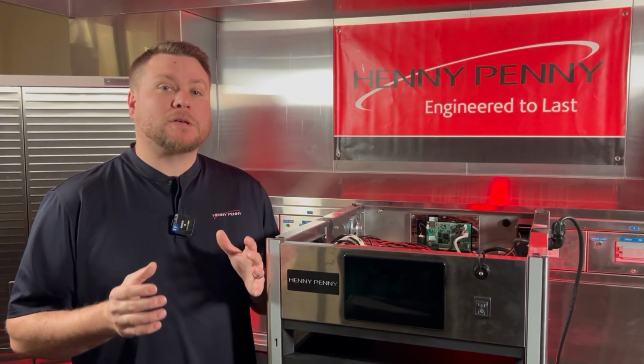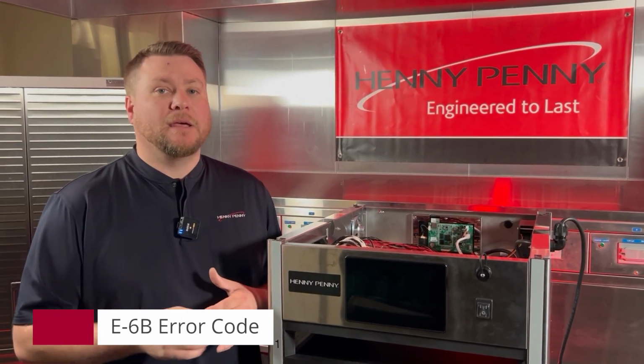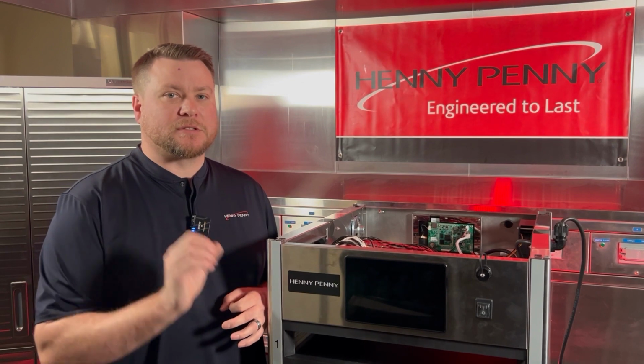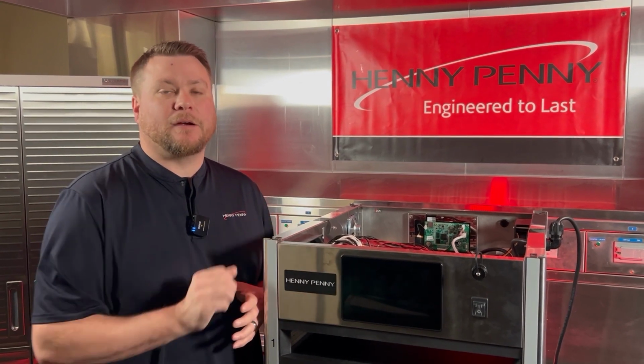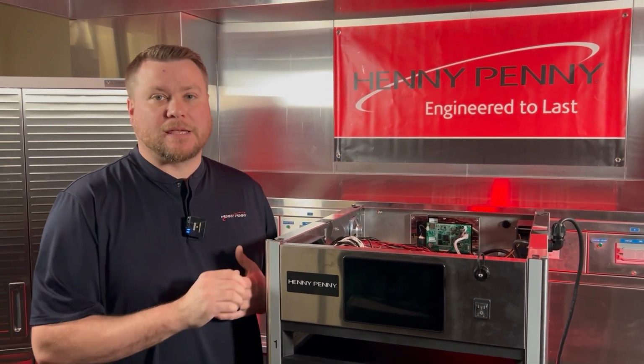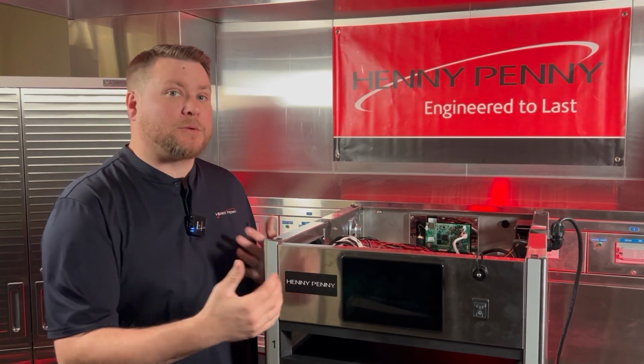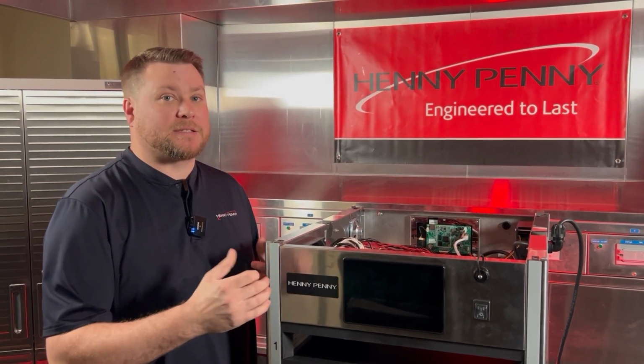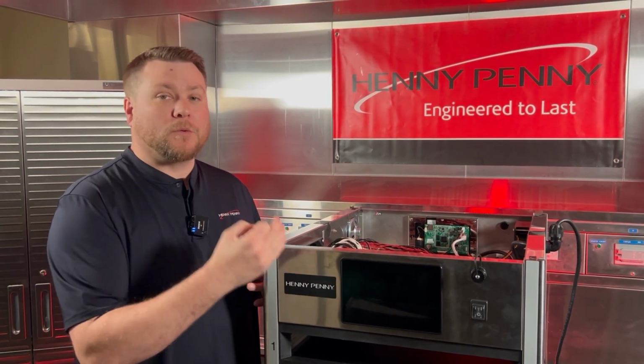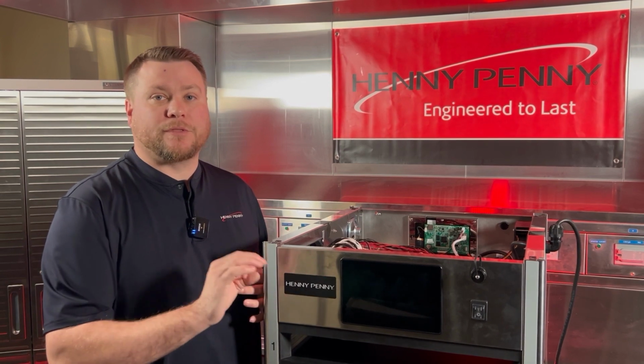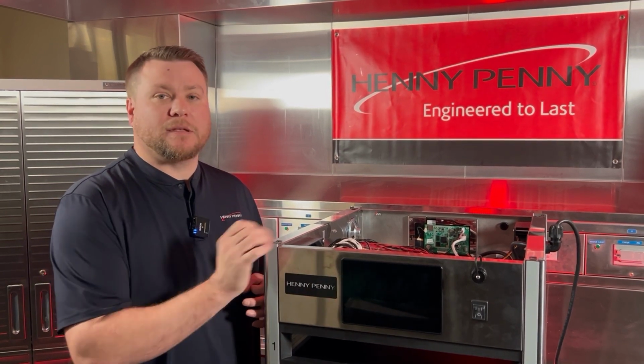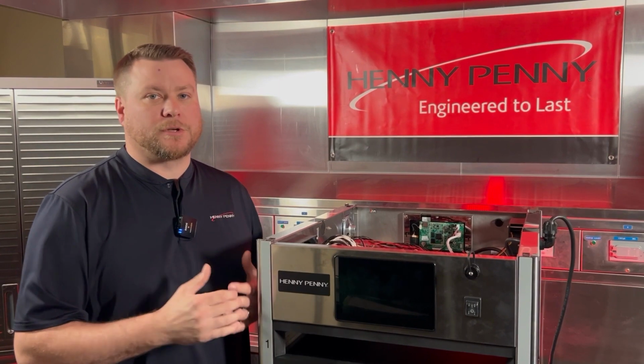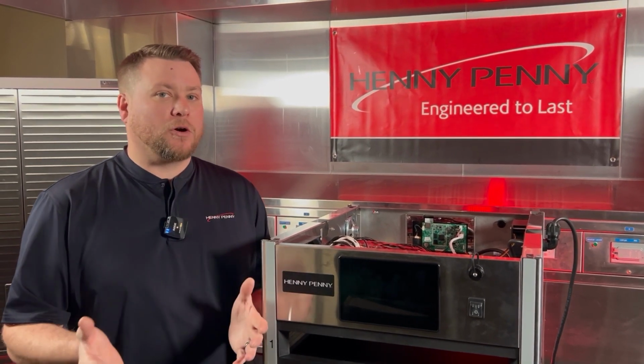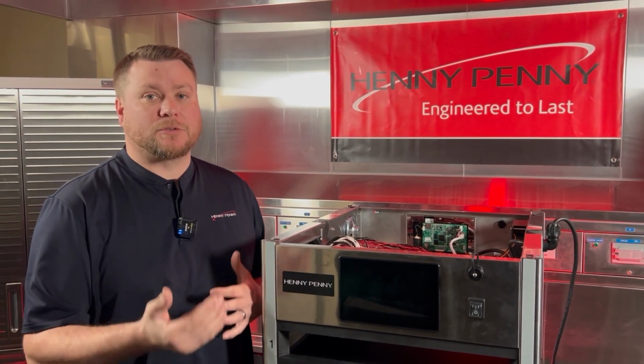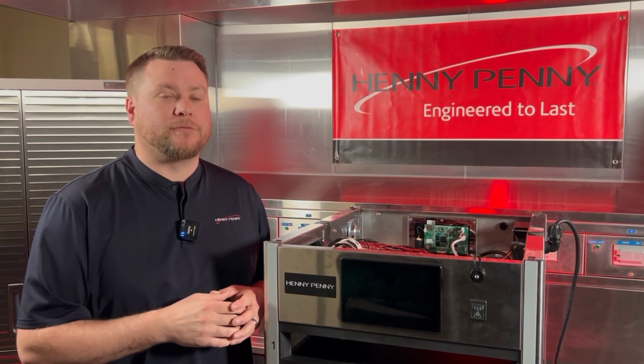In this video, we're going to talk about the E-6B. Now the E-6B is just slightly different compared to the A error code. And basically what this is saying is any one of those probes that we just talked about in the E-6A video, any one of those probes, with the B variant, is going to mean that any of those probes are shorted internally. So instead of it being an open circuit, it's saying that it's shorted internally and it's an internal fault.